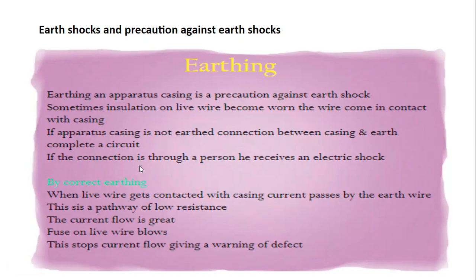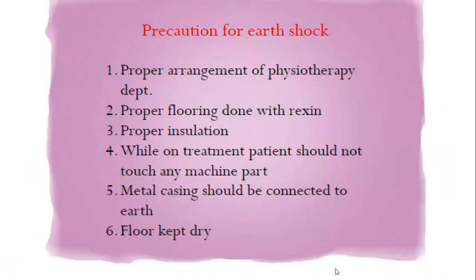If the connection is through a person, they receive an electric shock very easily. So by correctly earthing the apparatus, when a live wire contacts the casing, current can pass through the earth wire, which provides a pathway of low resistance. The current flow could be huge, so the fuse on the live wire blows, stopping current flow and giving a warning of the defect.